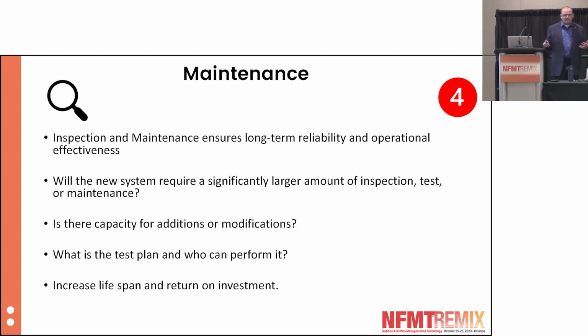I know of a situation where someone used value engineering, VE. The plan was to install 120 VESDA air sampling systems in this building, and you're thinking that's big dollars—and it is. So instead, they decided to install spot smoke detectors. That's cheaper, right?